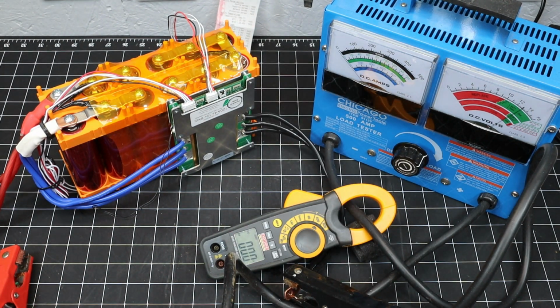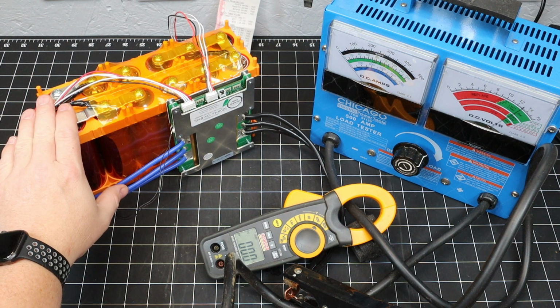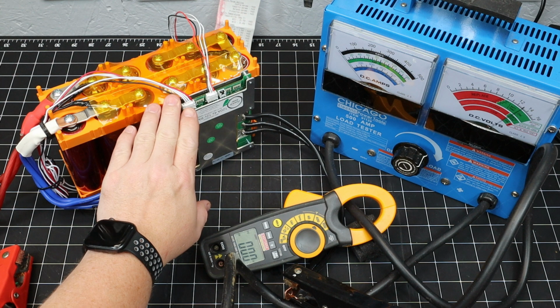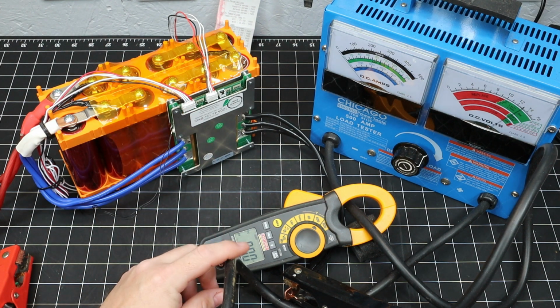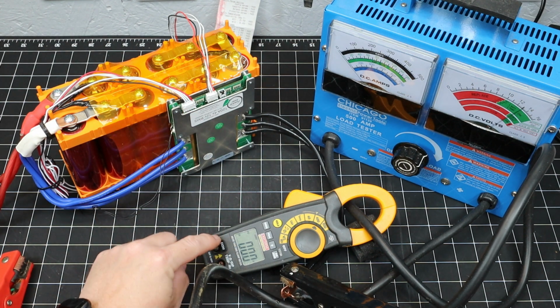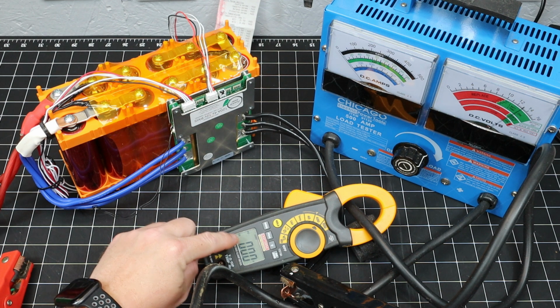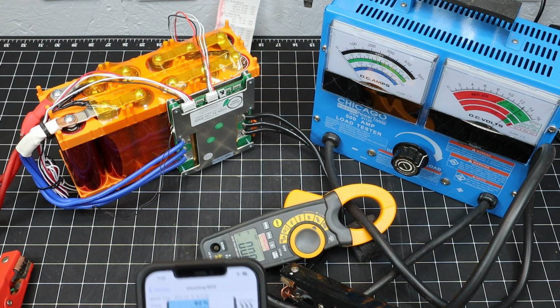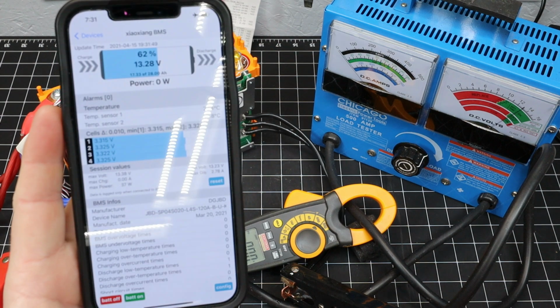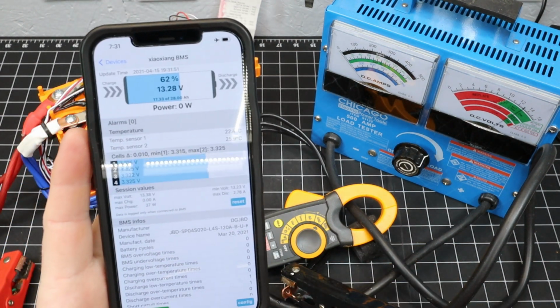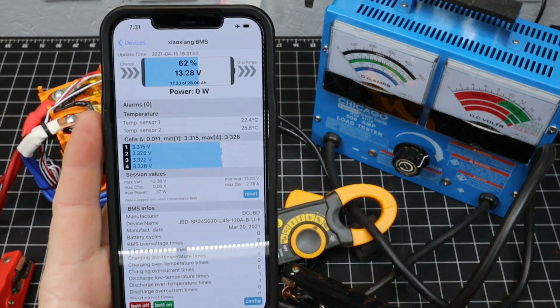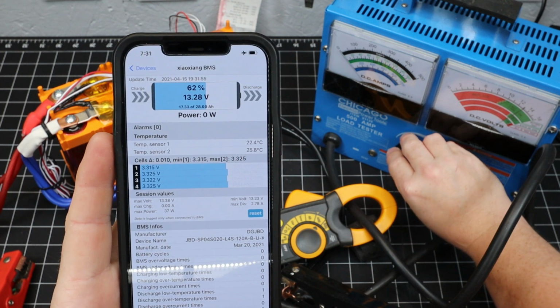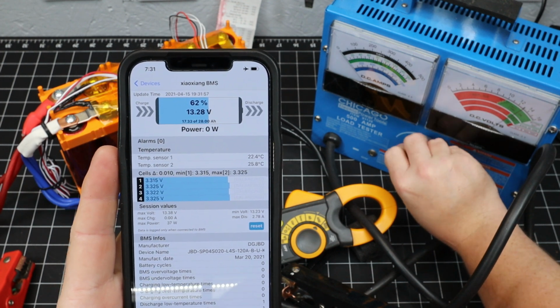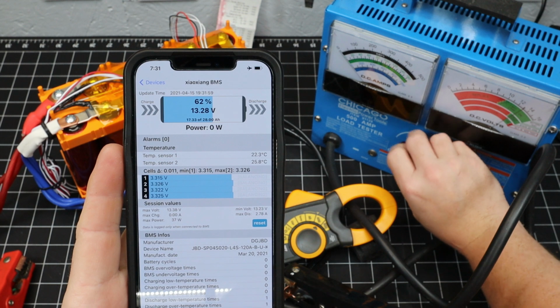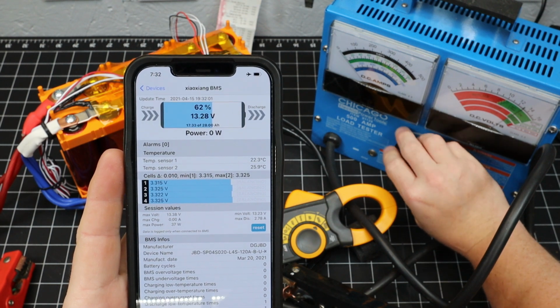Let's pull a true 120 amps. Not only are we testing the headway batteries, but we're testing the BMS. I've got the amp meter zeroed out in DC, and I'm going to try to do this while keeping my phone recording over here to see if we can pull a load. We'll start out low, pulling like a 20 amp load.